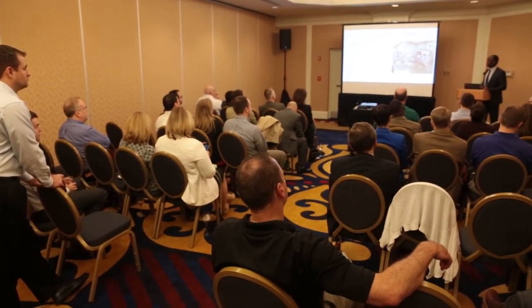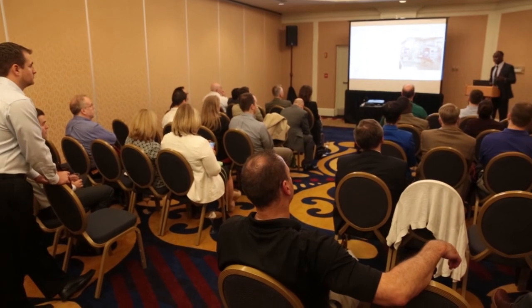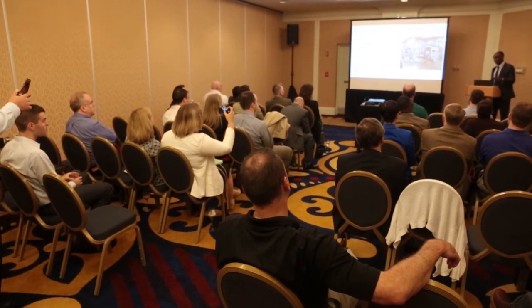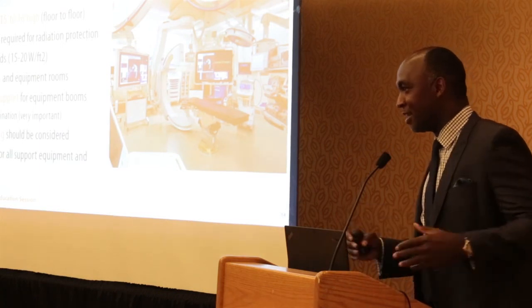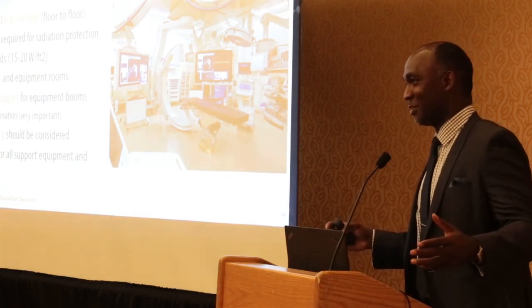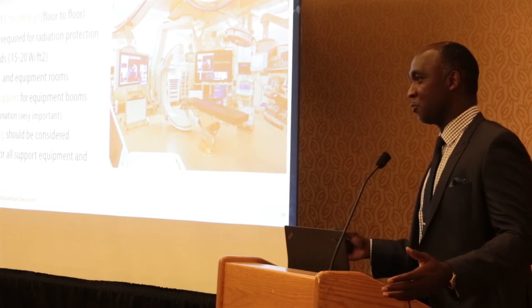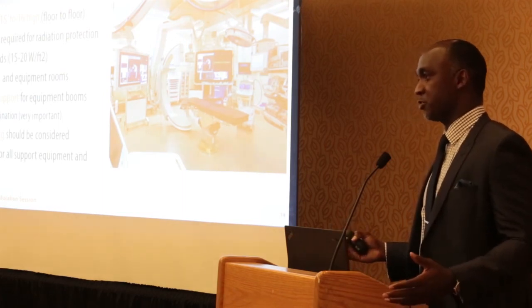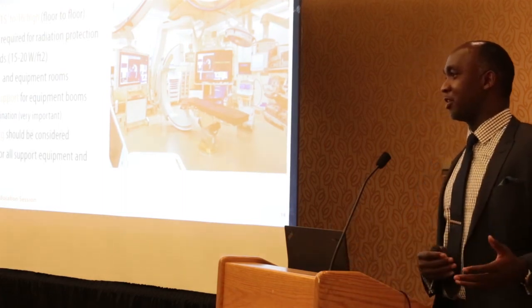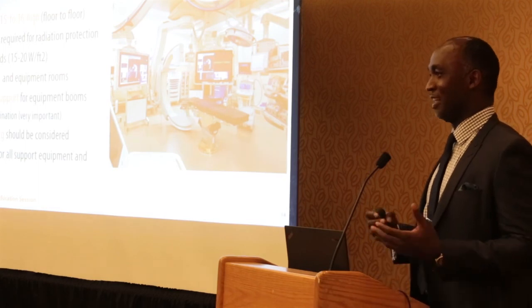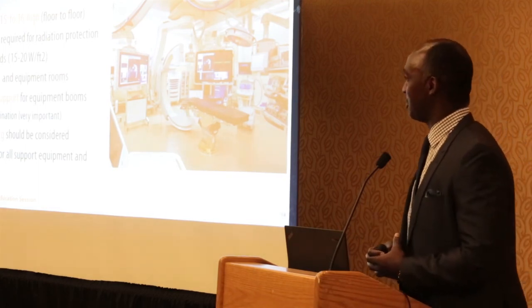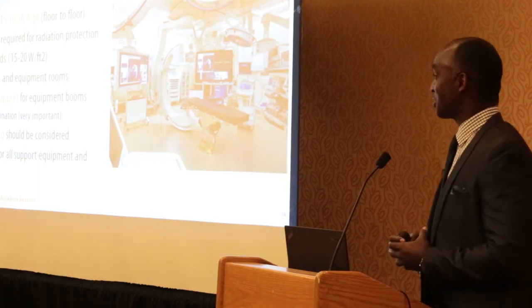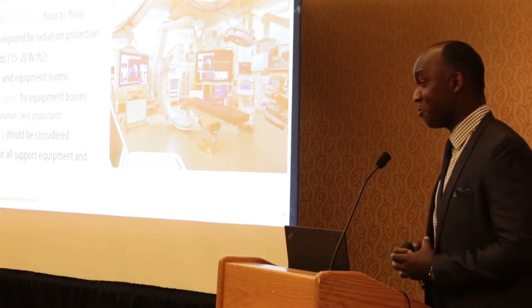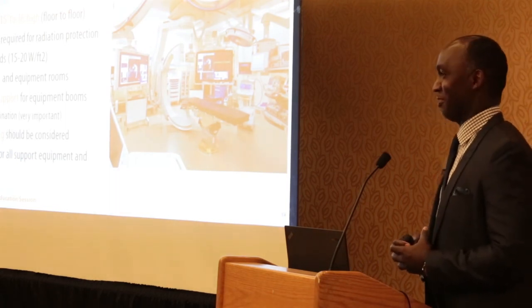And also, as I said, you have to have a separate control equipment room. The code says it's possible and it's likely. It's absolutely necessary. You don't design an MRI without a control room. You have to have a control room. So you have to add another 120 square feet to your space. Structural coordination is extremely important. The equipment is extremely heavy.